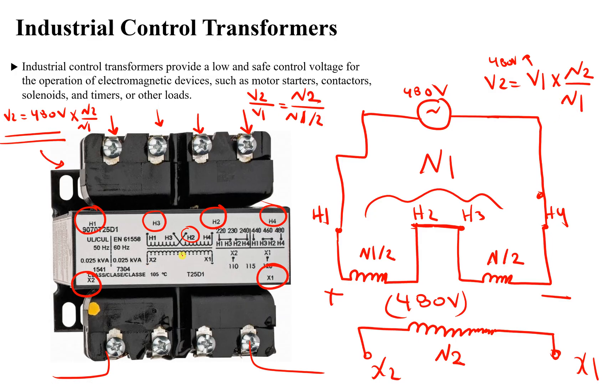So if you have a supply in the 220–240V range, use the parallel connection, and if you have a supply in the 440–480V range, use the series connection. Both configurations give you the same output voltage — that's the key advantage of this design.